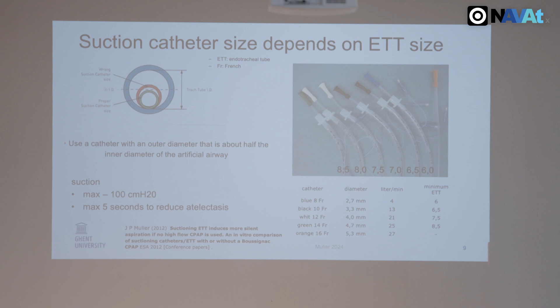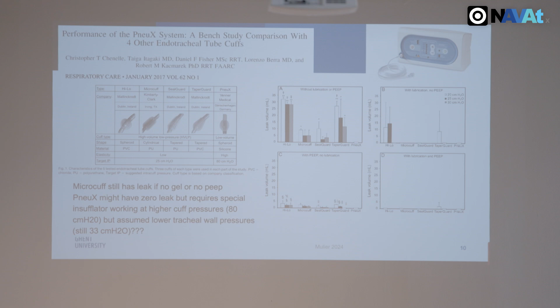A new tube was also recently developed, the PneuX, which has a special controller, and we go to very high pressures in the cuff, but they measured the tracheal wall, and they said that for a pressure of 80, you only have a pressure of 30, 35 against the wall. But they do not measure that continuously, so you're not fully aware. But with these higher pressures and a balloon, again without any plicae, you might have no leak or zero leak. But we are not absolutely sure that these wall pressures stay that low, and that's theoretical. So I'm a little bit afraid to start using that. You also need special tools to get these values. That's why I think we still have a real problem.